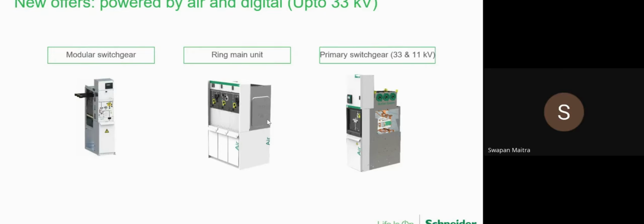And this is the tank here, and it is throughout, end to end. There is a single tank. So the ring main unit comes within a single tank, and the gas insulated switchgear panels come in different separate tanks. This is the difference between a ring main unit and 33 kV gas insulated switchgear panels. Why is it a ring main unit? Similar types of equipment are installed at a distance, maybe 1 kilometer, or maybe every 500 meters there can be a ring main unit. From here the cable will come and go to another ring main unit. From the previous one to here and from here to there, and the middle one will give the supply to the local transformer. So this is the concept of a ring main unit. These are primary switchgears and these are modular switchgears.